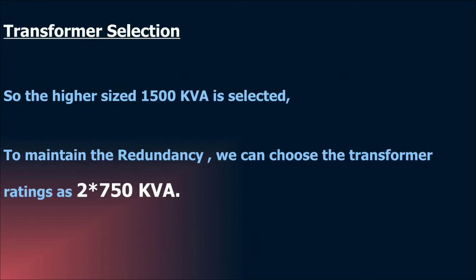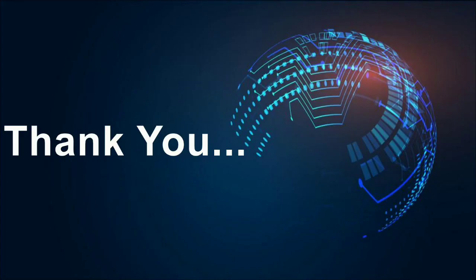While analyzing the two methods, we have seen that in the first method, the transformer rating was arrived to be 1000 kVA, and that in the second case was 1500 kVA. So we need to go ahead with 1500 kVA. In order to maintain the redundancy of the system, we shall choose two numbers of 750 kVA transformers. This was all about the selection of supply voltage and the selection of transformer rating. In the next video, I will be discussing the rest of the parameters related to a transformer.